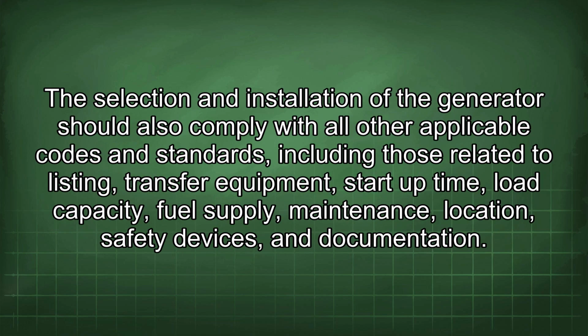The selection and installation of the generator should also comply with all other applicable codes and standards, including those related to listing, transfer equipment, startup time, load capacity, fuel supply, maintenance, location, safety devices, and documentation.